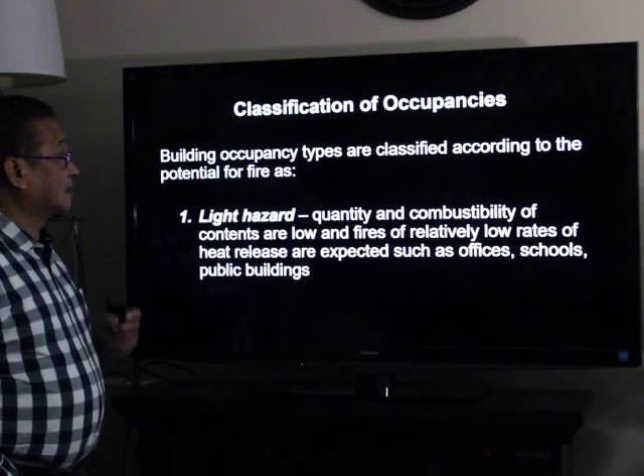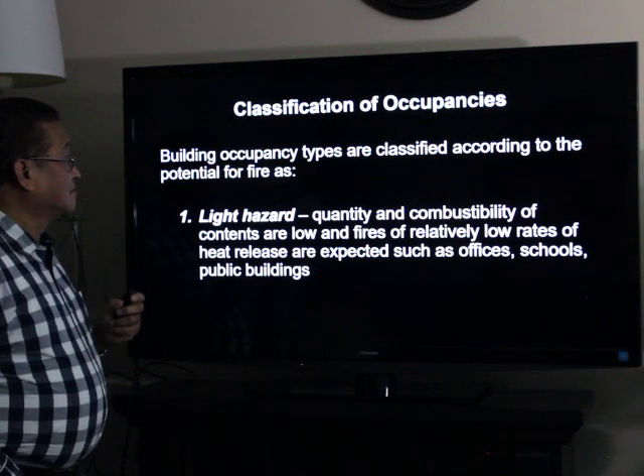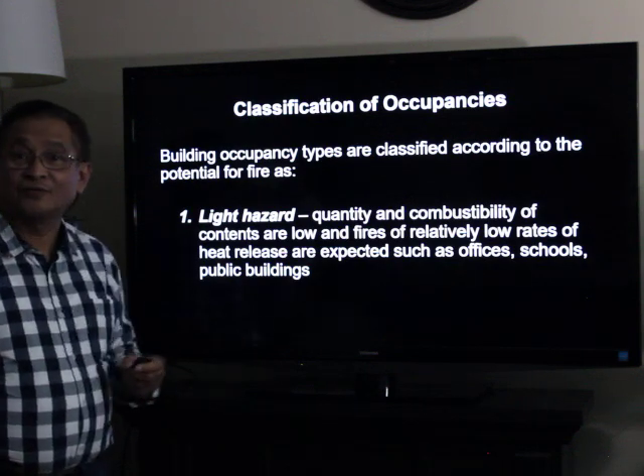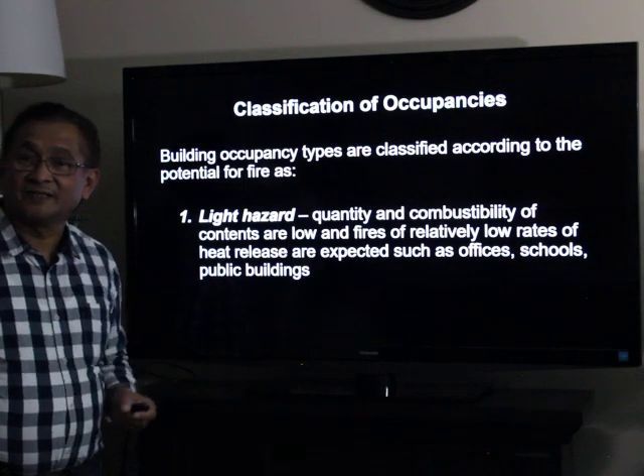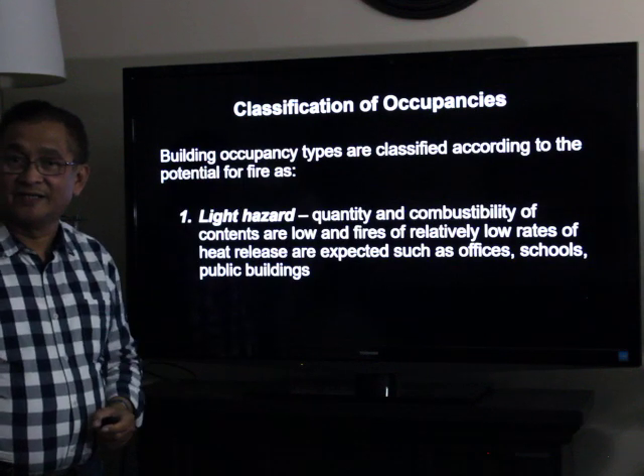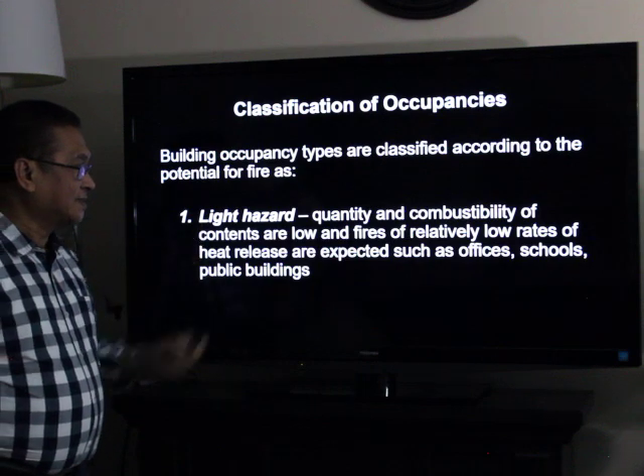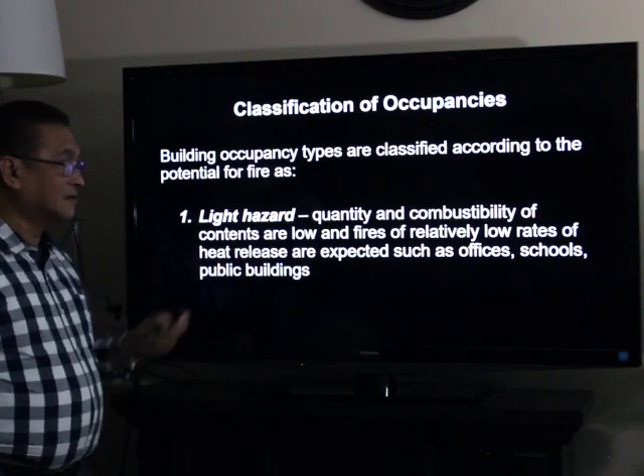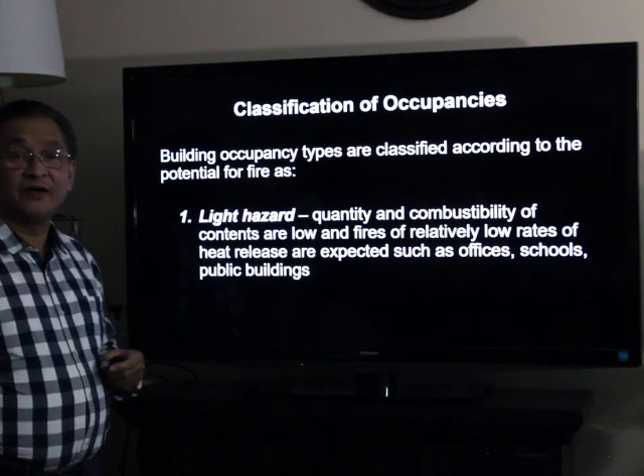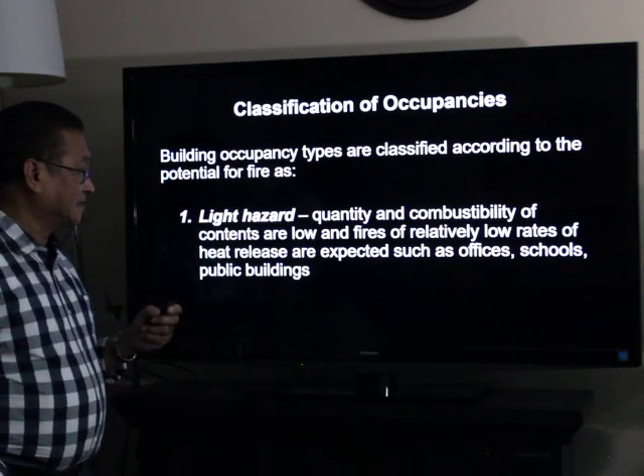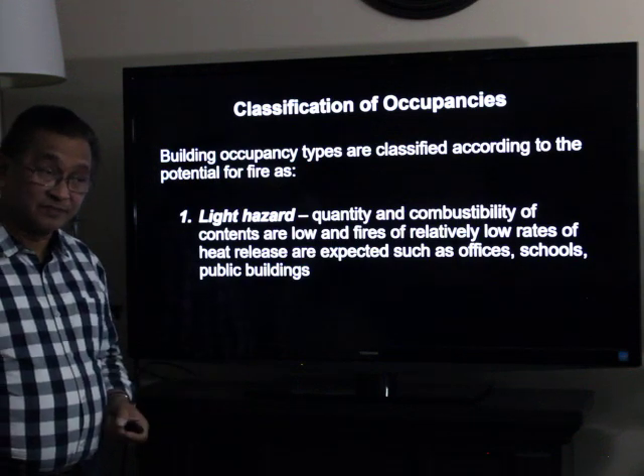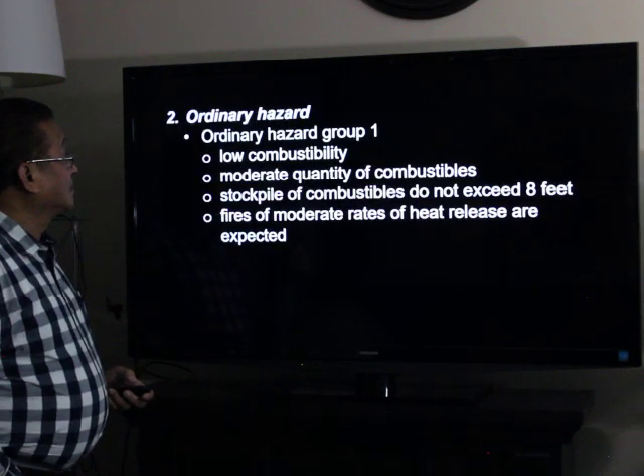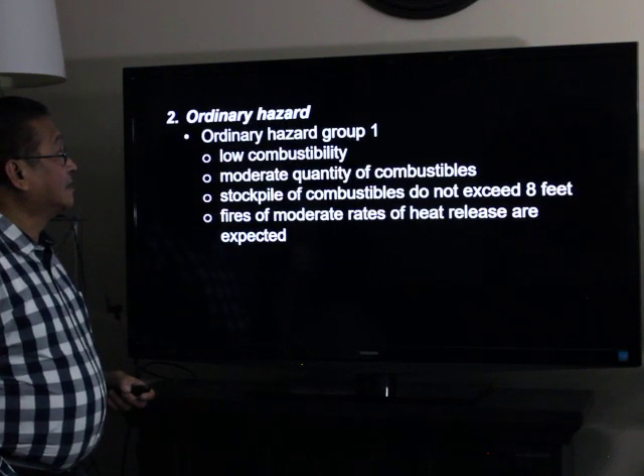Building occupancy types are classified according to the potential for fire as follows. We have three main ones: light hazard, ordinary hazard, and extra hazard. For light hazard, the quantity and combustibility of the contents are low, and fires of relatively low rates of heat release are expected. Examples include offices, schools, and public buildings. Ordinary hazard has two groups.